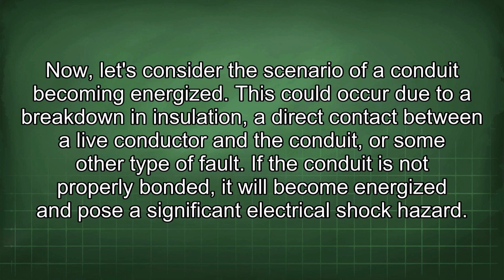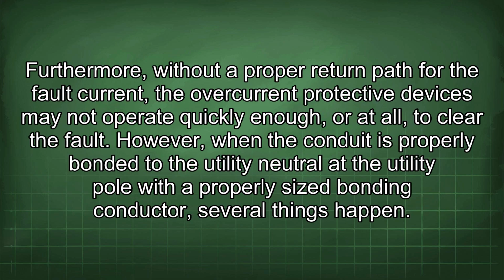This could occur due to a breakdown in insulation, a direct contact between a live conductor and the conduit, or some other type of fault. If the conduit is not properly bonded, it will become energized and pose a significant electrical shock hazard. Furthermore, without the proper return path for the fault current, the overcurrent protective devices may not operate quickly enough, or at all, to clear the fault.